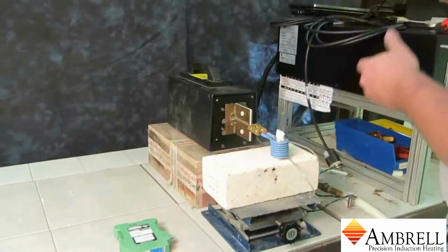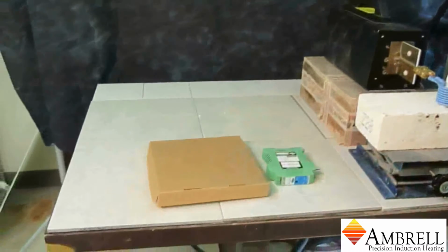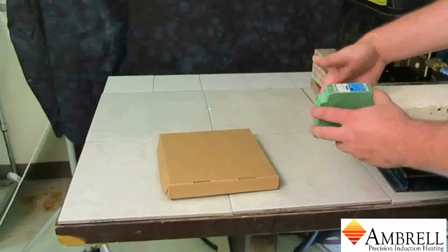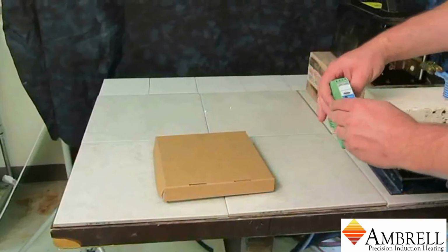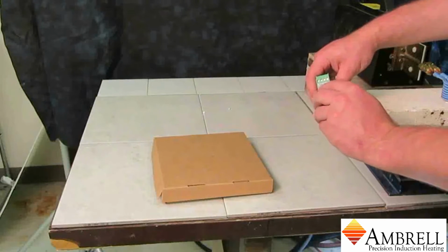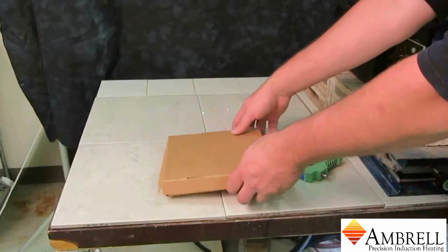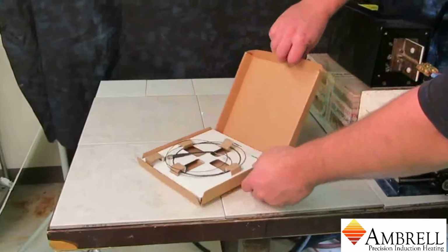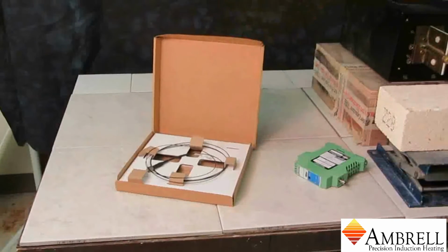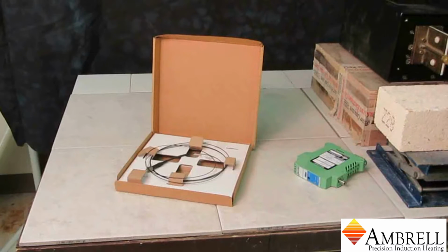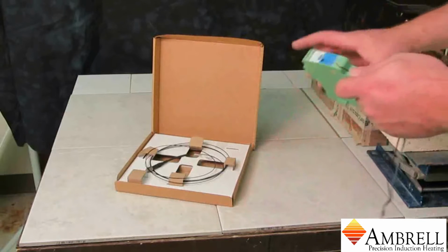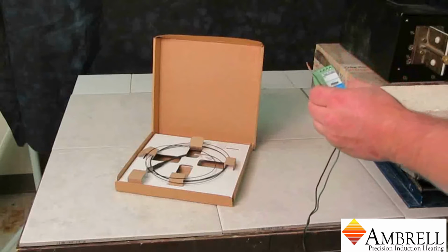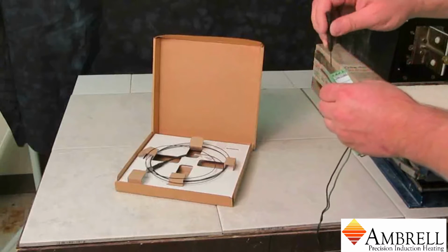If we're providing the Photon control unit, it looks like this. It comes with a fiber optic, and you'll need to provide 24 volts to the section that says power. It says plus minus, and it's relatively easy to figure out. This is the fiber optic probe. In this case, I use black as my ground and green as my positive. If you want to use red and black, that's fine too. It won't make a difference.